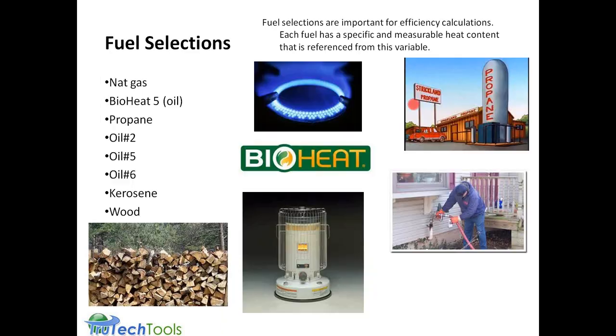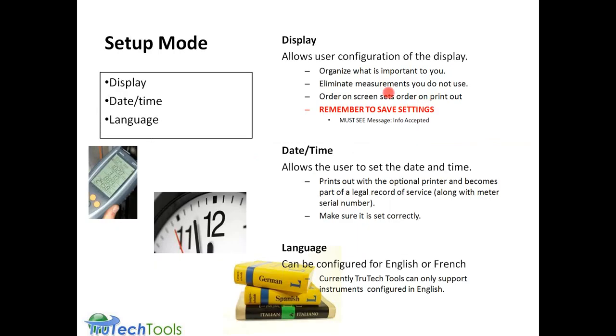When you go through the display setting, you'd basically indicate which parameter you want to change on the display. And you would scroll down to the parameter that you want to change, and that line would then flash, the number beside it would flash in the corner of the screen. You would then press the buttons at the bottom to change the parameter and use the up and down buttons to scroll through and pick which parameter you wanted. Then there's another button on the side which says units, and that units button would allow you to choose which unit of measure. So that's where you could switch from inches of water to Pascal.